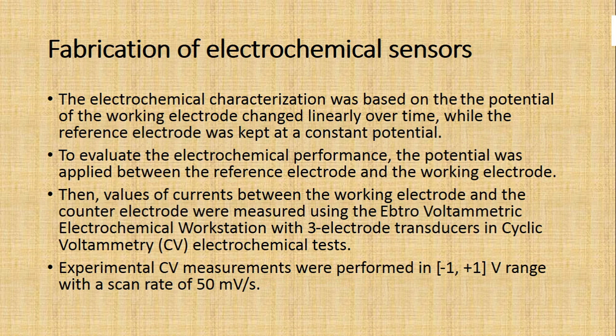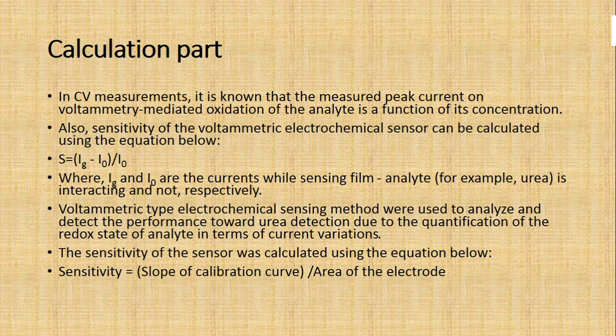The potential of the working electrode was changed linearly over time. The reference electrode was kept at a constant potential. Using three-electrode transducers in cyclic voltammetric mode, the current values between working electrode and counter electrode were measured. The range was -1 to +1 volt and scan rate was 50 millivolts per second. The peak current is a function of the concentration of an analyte in the cyclic voltammetric oxidation.